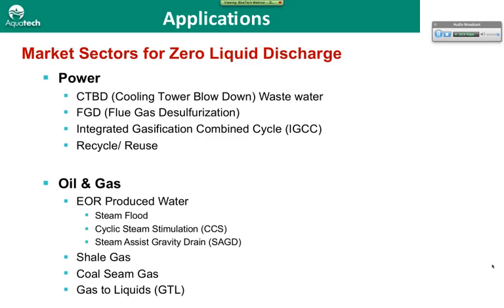With FGD, I'll cover that in a little more detail later. The gasification wastewater itself has widely varying chemistries, and it's linked to the type of coal used, the type of makeup water used, and is highly dependent upon the gasification technology. So it's very difficult to categorize gasification wastewater. You really need to know what type of gasification technology is being applied to get a prediction on the blowdown that has to be treated, from the gasification supplier.